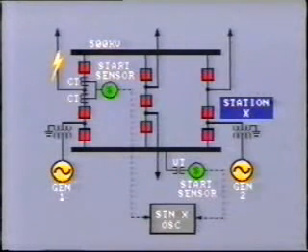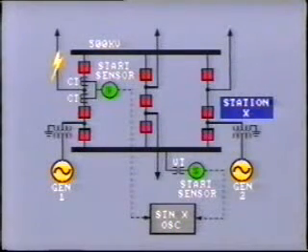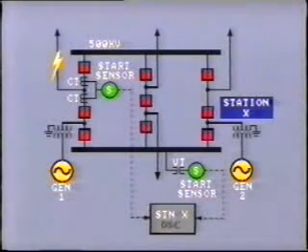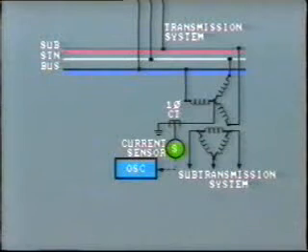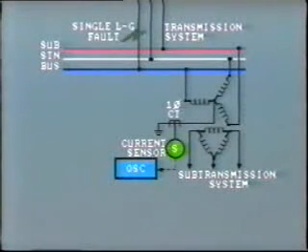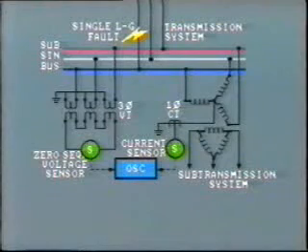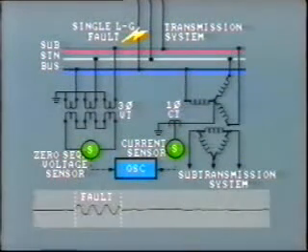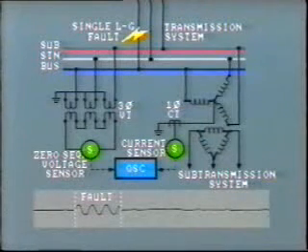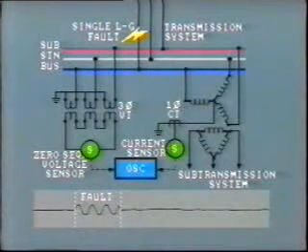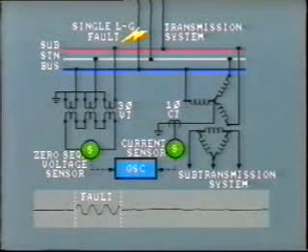The most important accessory is the starting sensor — basically a relay which continuously monitors the power system and detects disturbances such as faults and power swings. Fault sensors are the most common type, typically responding to over-current or under-voltage. For example, an over-current sensor in the neutral circuit of a transformer detects single line-to-ground faults. This sensor is often backed up by a zero-sequence voltage sensor connected across the broken delta winding of a voltage transformer. This measured voltage is zero under normal conditions but greatly increases for a line-to-ground fault, allowing the voltage sensor to be set very sensitively as good backup for the current sensor.